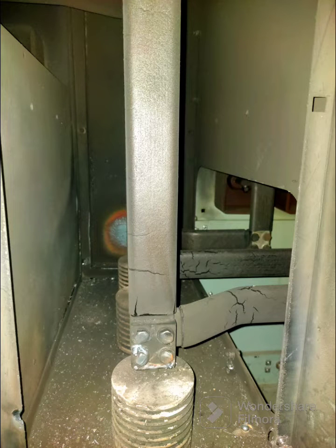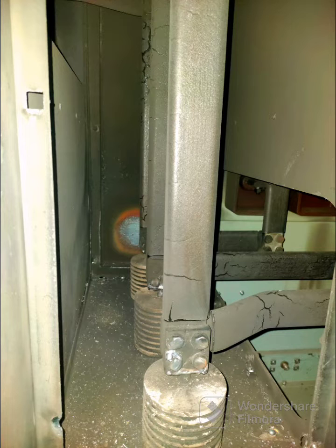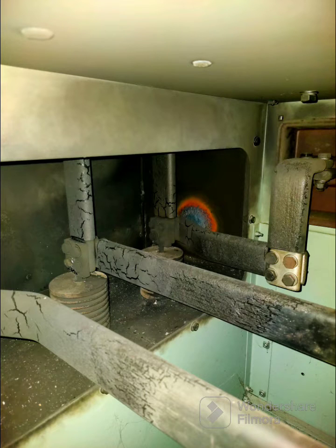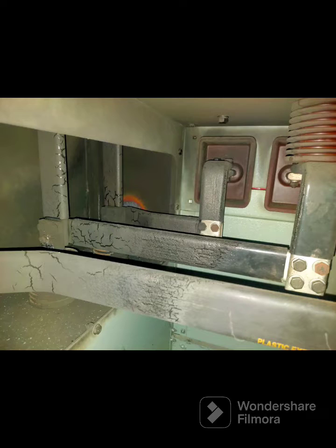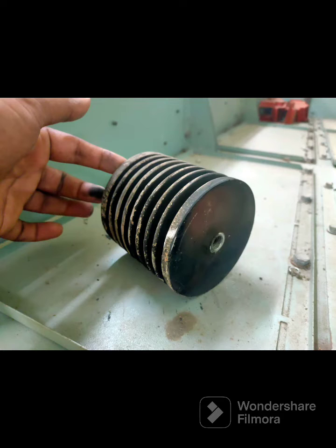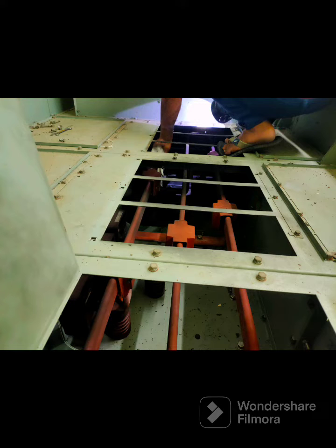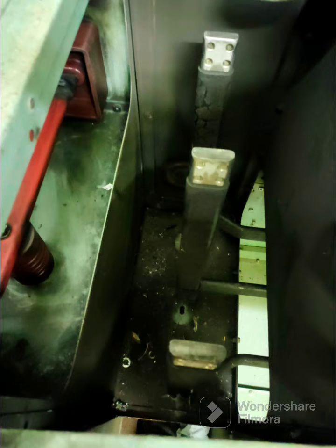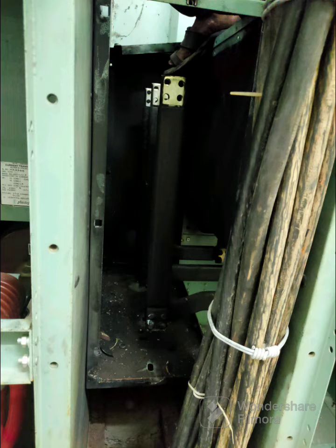The bus post insulators inside the panels have been affected, and the upper part epoxy has been affected, also the spout. The BPI has been dismantled, and you are seeing the affected BPI. The work is starting for the renovation, retrofitting and modifications of the panels, adjustment of the new BPI, and cleaning and painting inside the panel.